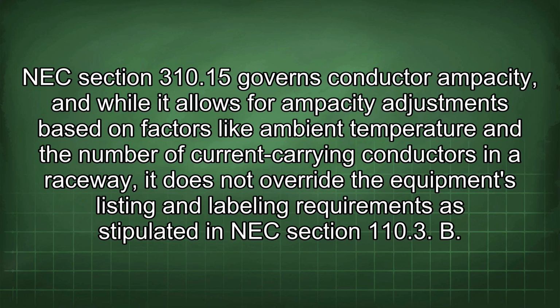NEC section 310.15 governs conductor ampacity, and while it allows for ampacity adjustments based on factors like ambient temperature and the number of current carrying conductors in a raceway, it does not override the equipment's listing and labeling requirements as stipulated in NEC section 110.3.